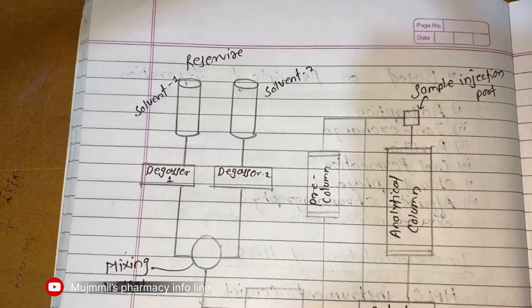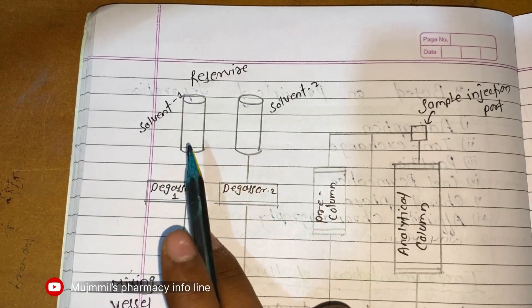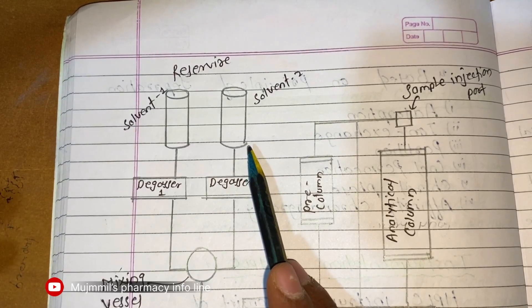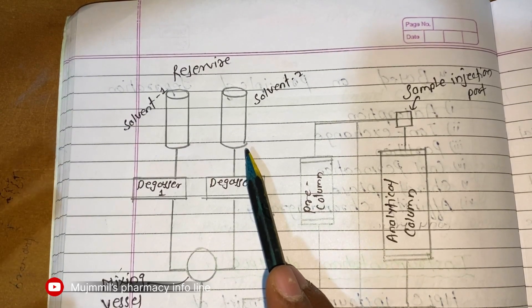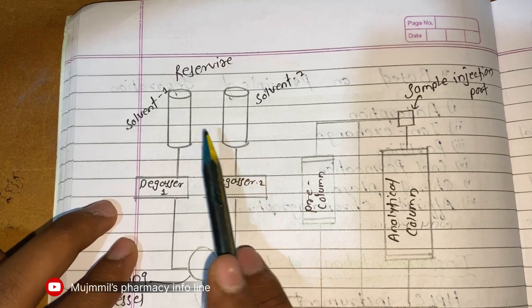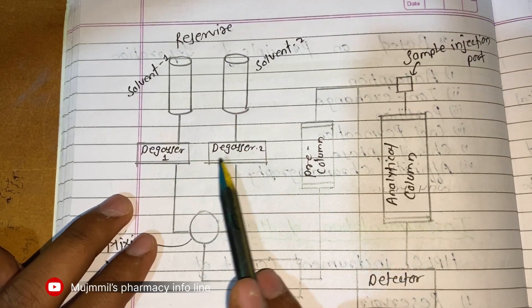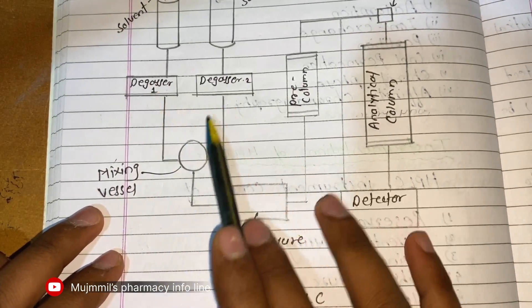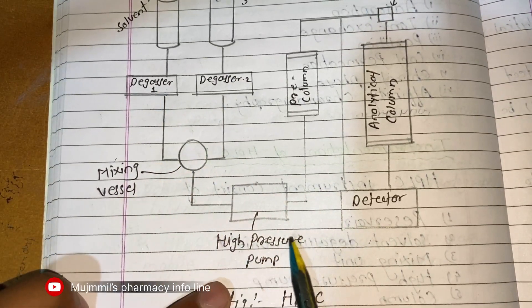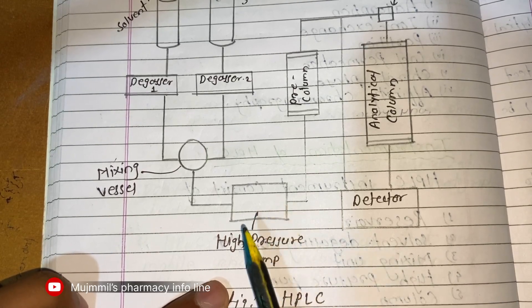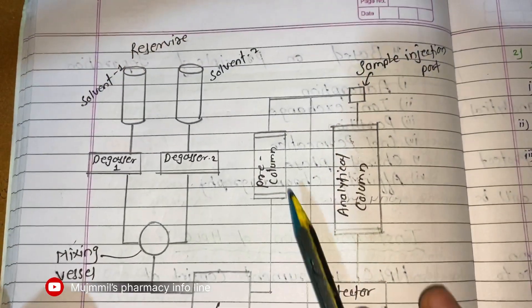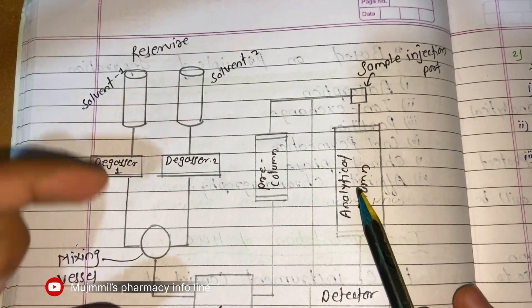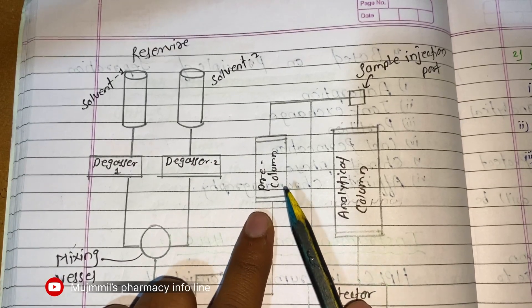Looking at the diagram of HPLC: two solvent reservoirs can be used — in fact two or four solvent reservoirs depending on the instrumentation. After the solvent reservoir, there are two degasser units, then a mixing vessel attached to the degassing unit. From the mixing vessel, a high pressure pump is attached for pumping the mobile phase into the column. There is a pre-column, which is smaller compared to the analytical column.